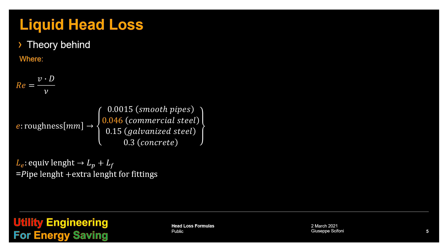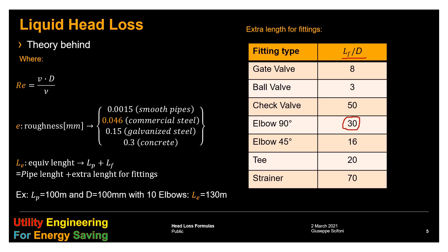For instance, if we have a pipe of 100 meters and 10 elbows at 90 degrees, the table says any elbow is equivalent to 30 times L over D. We need to increase 30 times 10, 300, times the diameter D, the size of the pipe, 30 meters. So the equivalent length is 100 plus 30.